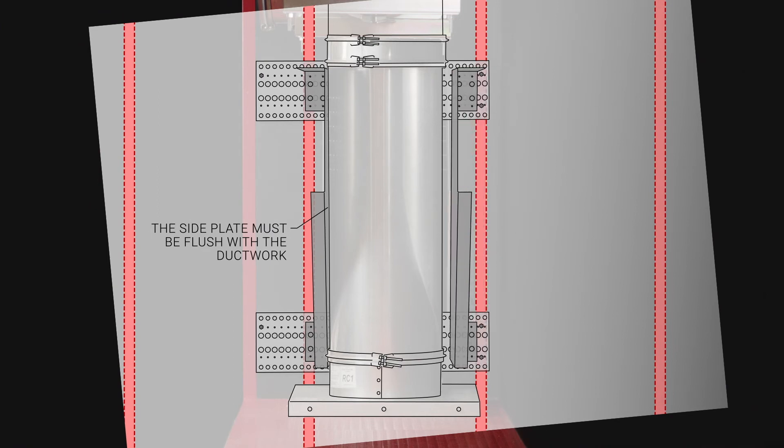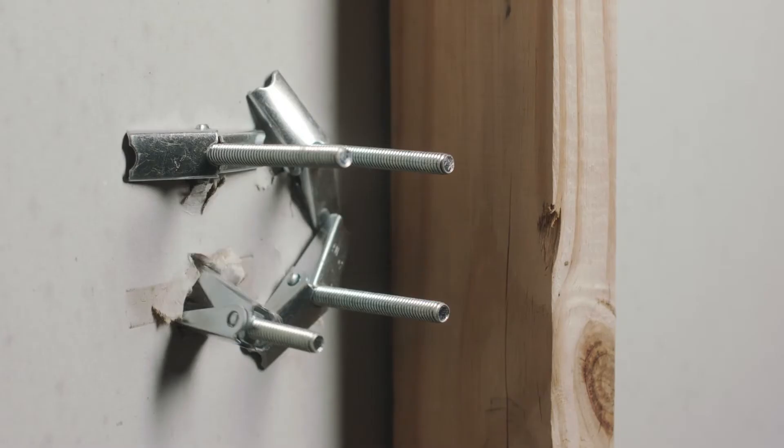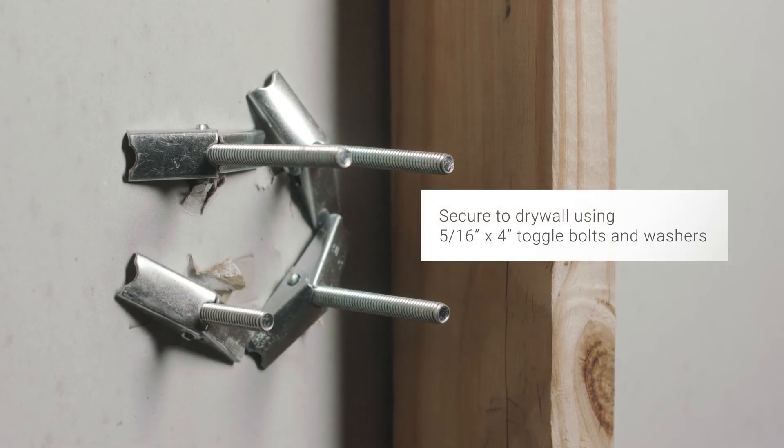Install the second side plate to the wall. You must install the plate flush with the ductwork. This plate will likely fall between two studs and if so, secure using five sixteenths by four inch toggle bolts and washers.